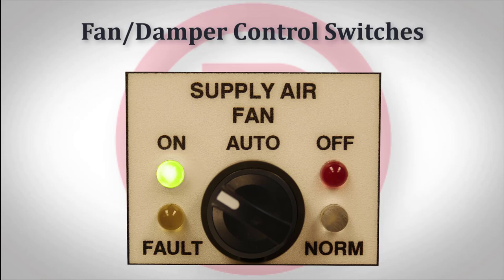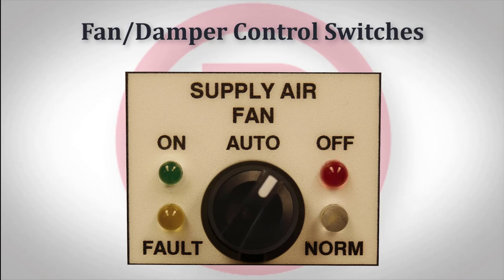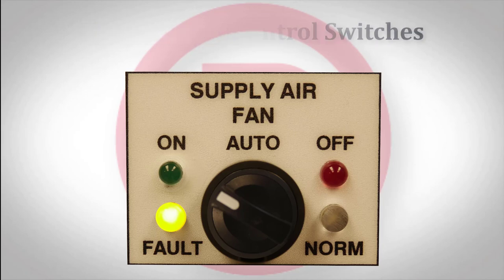To manually turn off or close the fan or damper, turn the key to the off or closed position. Once the panel sees a positive off or closed feedback from the fan or damper, the off LED will illuminate. The fault LED will illuminate if the panel does not receive a positive feedback signal from the fan or damper.